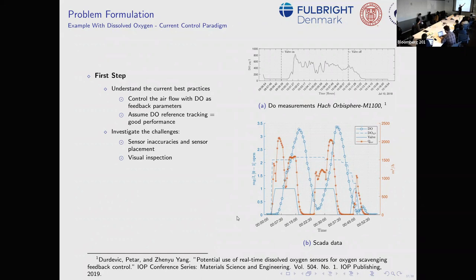Here is an example of dissolved oxygen measured with very high precision. One of the big issues is that when you open the valve there's a large and varying delay in the measurement. In our earliest work, we modeled the airflow in the pipelines, the diffusers, and modeled dissolved oxygen as a first-order plus dead-time model — it was quite a good model — but we quickly figured that modeling every aspect this way would only work for one plant, and if something changed we'd have to start over. That's why we turned to deep learning.